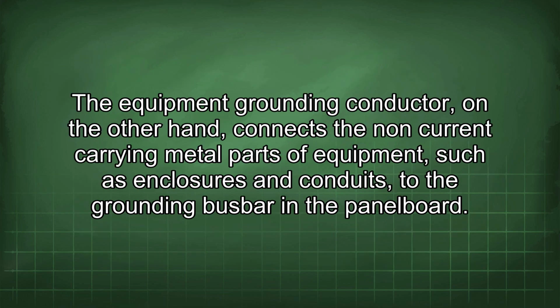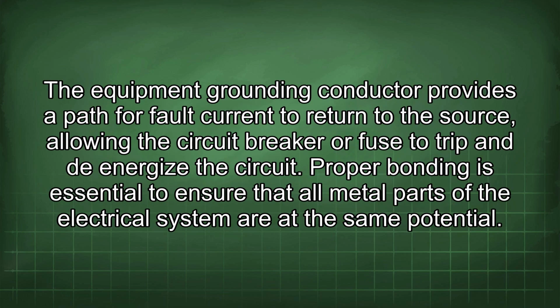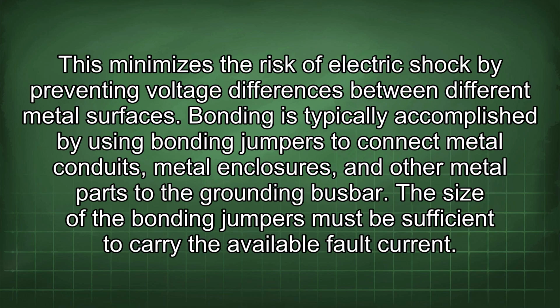The equipment grounding conductor, on the other hand, connects the non-current carrying metal parts of equipment, such as enclosures and conduits, to the grounding busbar in the panel board. The equipment grounding conductor provides a path for fault current to return to the source, allowing the circuit breaker or fuse to trip and de-energize the circuit. Proper bonding is essential to ensure that all metal parts of the electrical system are at the same potential. This minimizes the risk of electric shock by preventing voltage differences between different metal surfaces. Bonding is typically accomplished by using bonding jumpers to connect metal conduits, metal enclosures, and other metal parts to the grounding busbar. The size of the bonding jumpers must be sufficient to carry the available fault current.